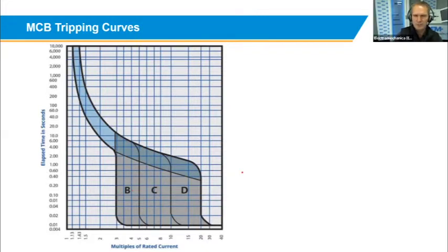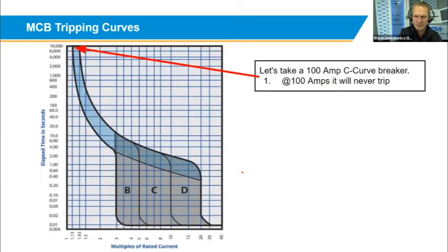So, for example, we'll take a 100 amp circuit breaker, a C curve, and just to prove to you that at 100 amps, it will never touch the tripping curve. So your 100 amps is 100% down there, and it will never touch this tripping curve. So your breaker, rated 100 amps, will run at 100 amps forever and will never trip. It will only start tripping, as you can see, from 113%, where it starts touching the tripping curve. So you can have a look at the time there, you talk about 10,000 seconds before this breaker might trip at 113%.